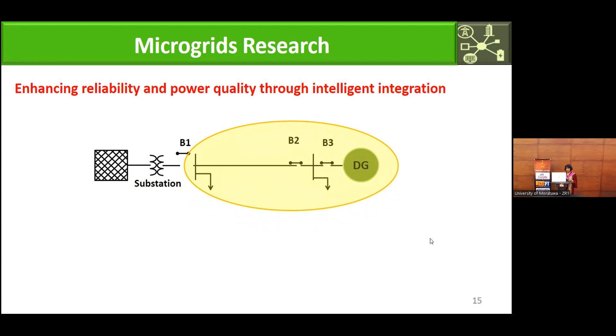Now with the microgrid concept coming in, standards have been set up to allow this power islanding. As I told you, we have to let the system control frequency and voltage when connected to the grid, and when islanded, there should be a source that can form the grid while others follow and feed in. To do that, we need some kind of islanding detection technique, and with these mode changes, we need energy management techniques and control to maintain system stability—there must be a seamless, smooth transition.